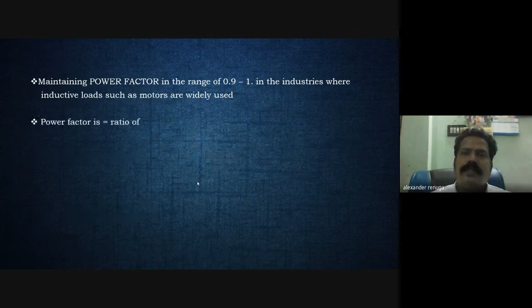Maintaining the power factor in the range of 0.9 to 1 in industries is a very important factor to conserve energy. Inductive loads such as motors are widely used, and in those the power factor gets reduced below 0.9. If it is reduced below 0.9, then TNEB levies penal charges, because whenever the power factor is reduced, it means the loss is more. So to avoid that, we have to maintain the power factor above 0.9.